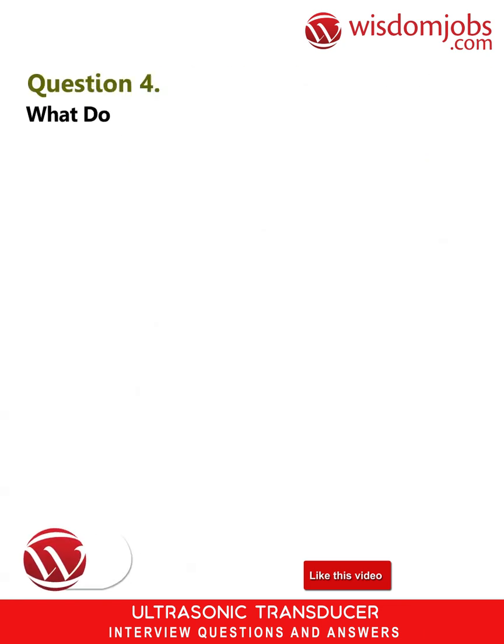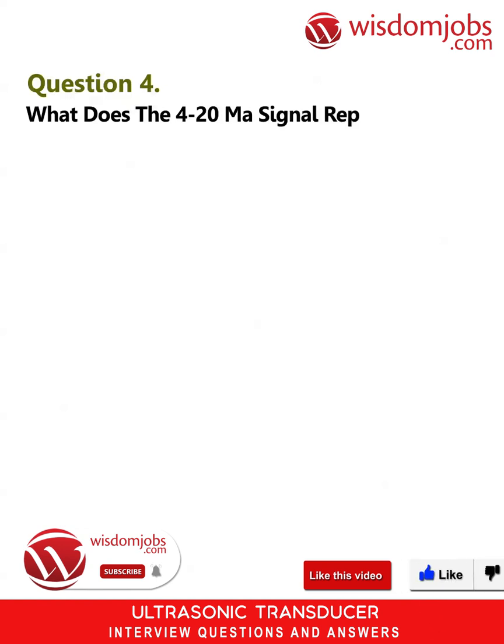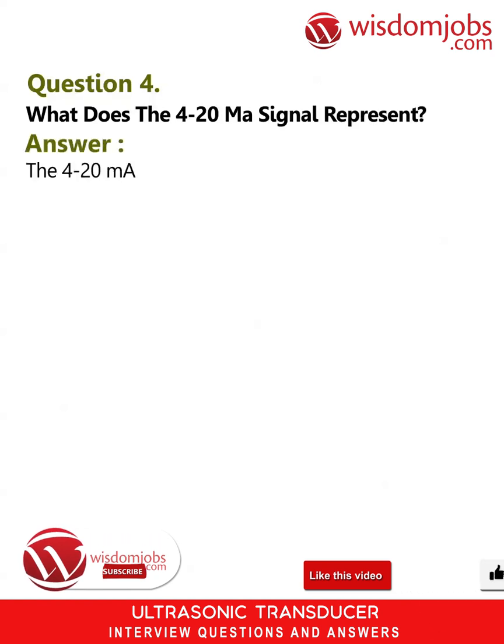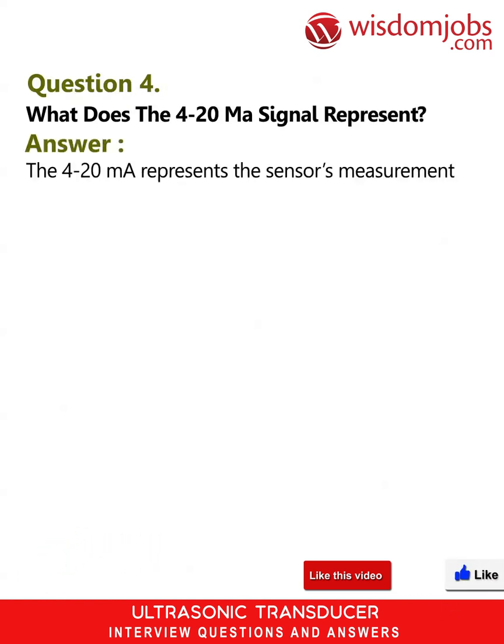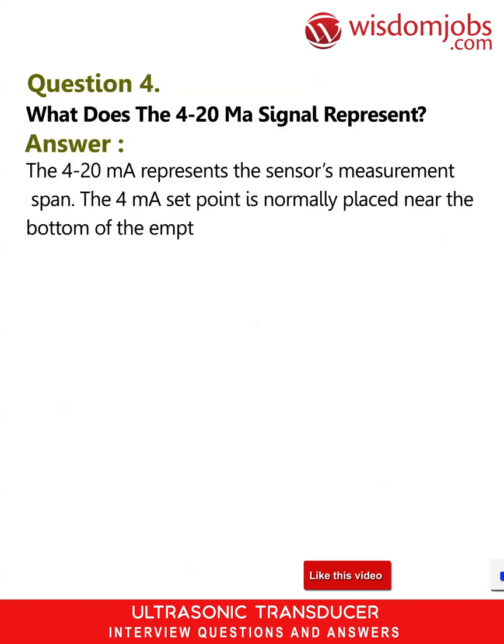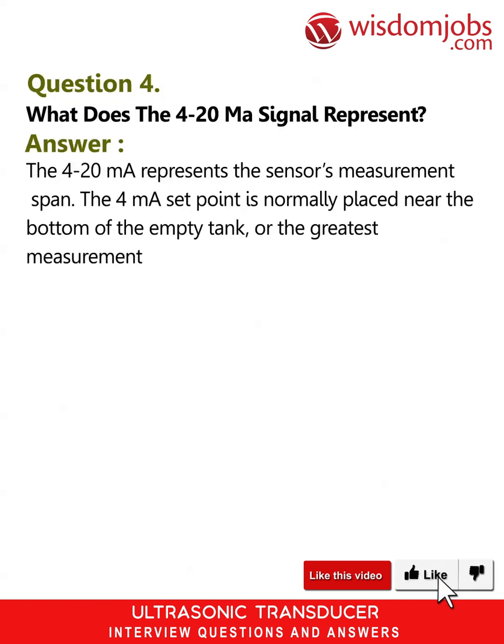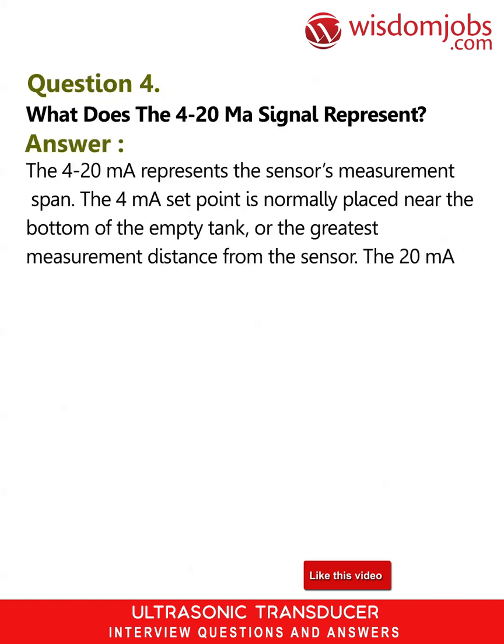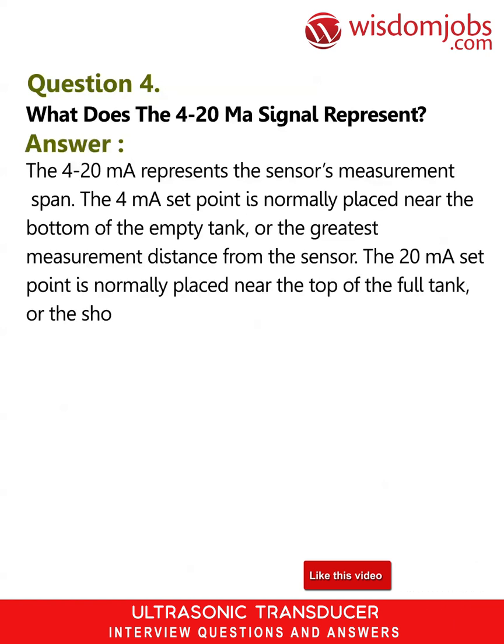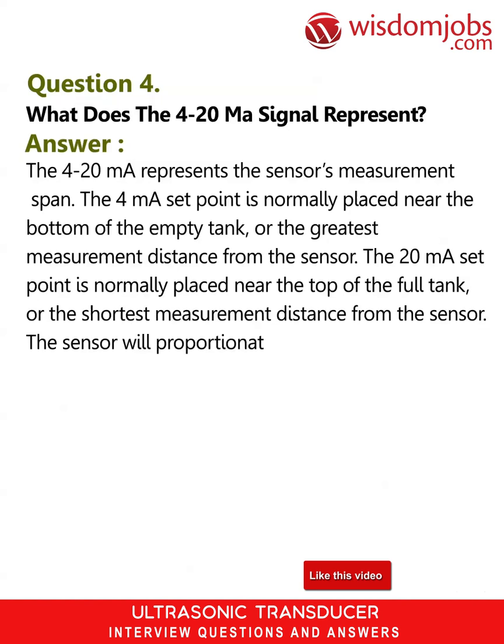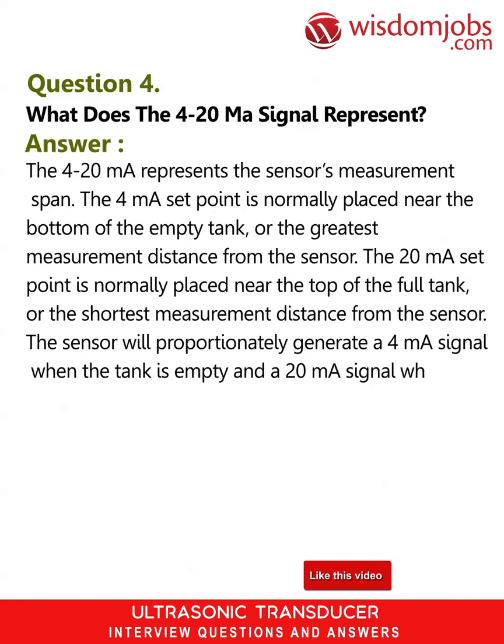Question 4. What does the 4 to 20 mA signal represent? Answer. The 4 to 20 mA represents the sensor's measurement span. The 4 mA set point is normally placed near the bottom of the empty tank, or the greatest measurement distance from the sensor. The 20 mA set point is normally placed near the top of the full tank, or the shortest measurement distance from the sensor. The sensor will proportionately generate a 4 mA signal when the tank is empty and a 20 mA signal when the tank is full.